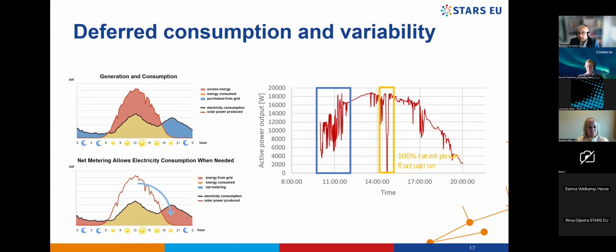Also, there are other kinds of issues we need to take into account. Here we have photovoltaic production. Ideally it would be a normal smooth function, but here we have a very huge oscillation. These oscillations are very typical on a cloudy day. In that case, the system must react to avoid any problem for the final customer, because the power drops a lot. Here, for example, in a very cloudy situation, we have a power fluctuation of 100% of rated power, but it's very sharp and very short.